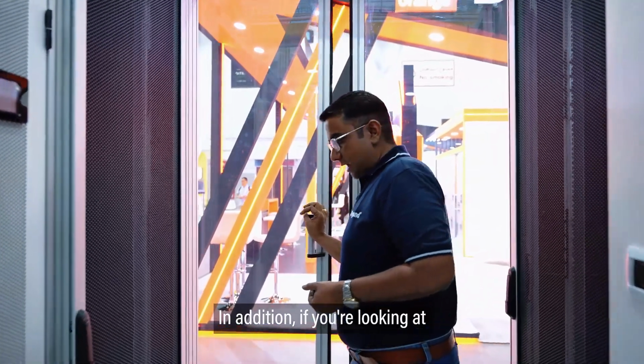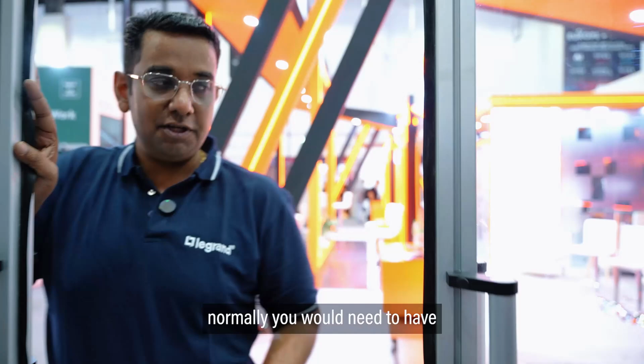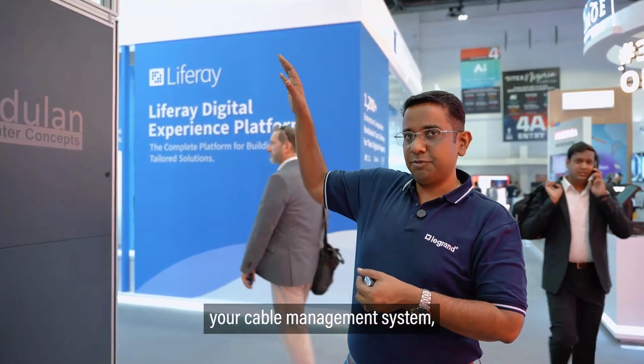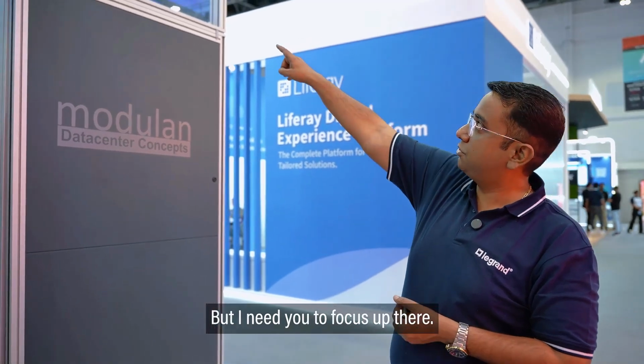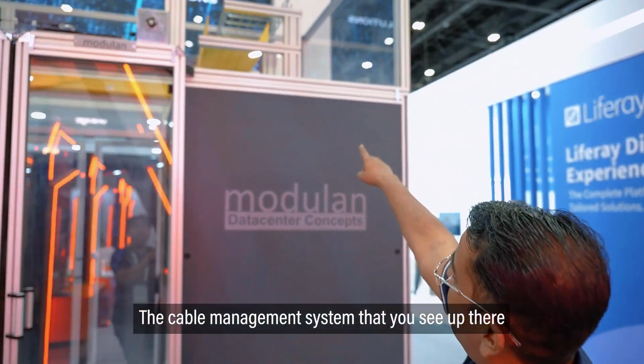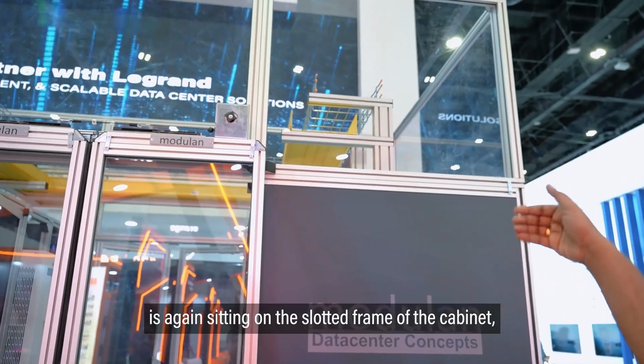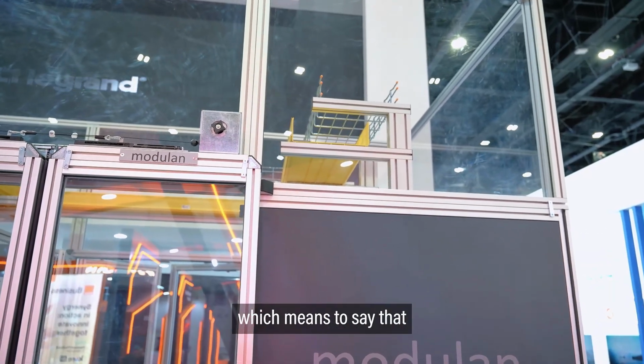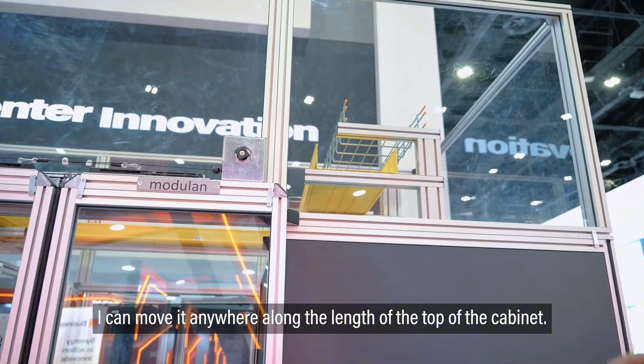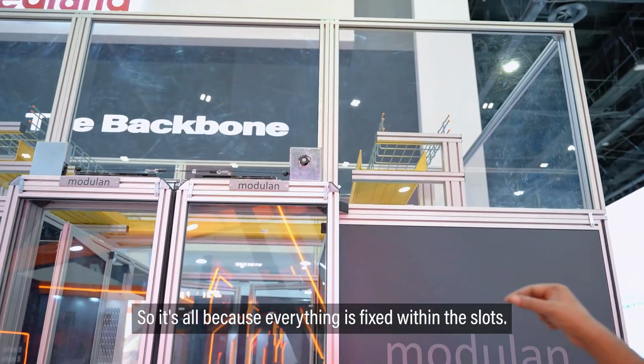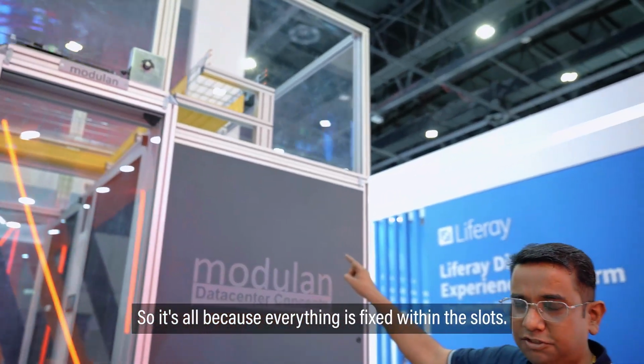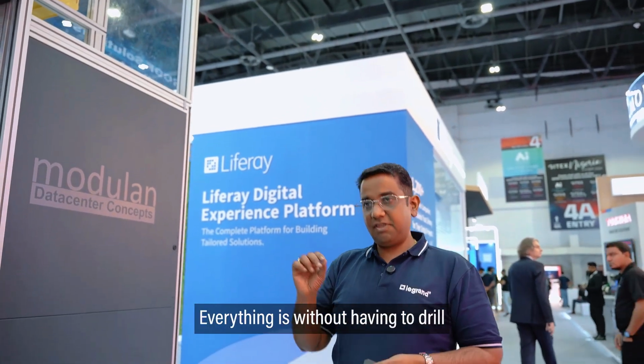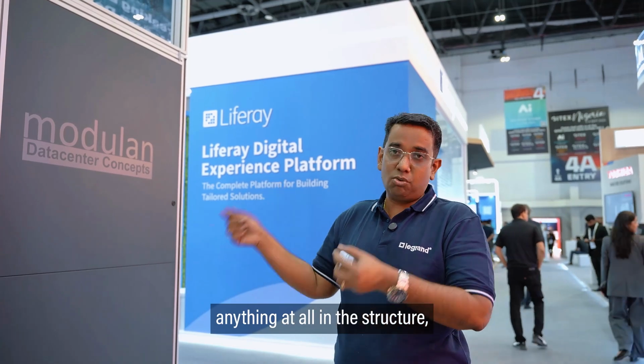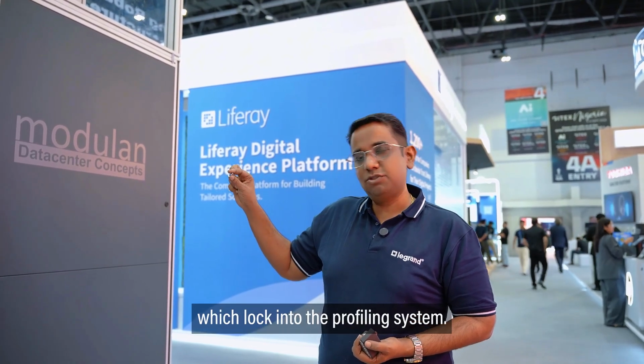If you're looking at further cable management, normally you'd need threaded rods hung from the ceiling to build your cable management system, wire baskets, and yellow fiber trays. But look up there: the cable management system you see through the hot aisle panel is sitting on the slotted frame of the cabinet, meaning I can move it anywhere along the length of the top of the cabinet, since everything is fixed within the slots. There are no screws used additionally, nothing is drilled into the structure at all. You use spring nuts and cage nuts which lock into the profiling system.